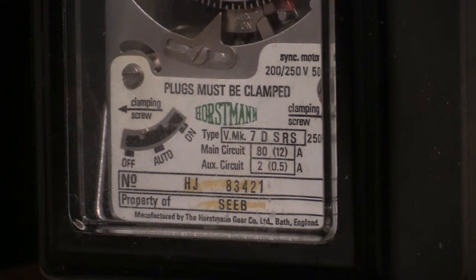So what we've got there is the VMK 7D SRS 200 to 250 volts with 50 hertz alternation frequency, which is very important for the synchro motor in order to make it run at the correct speed. The main switching capacity on that is 80 amps, and at 240 volts that is equivalent to 19,200 watts. The auxiliary circuit, which will be for the rate change trigger, is 2 amps.